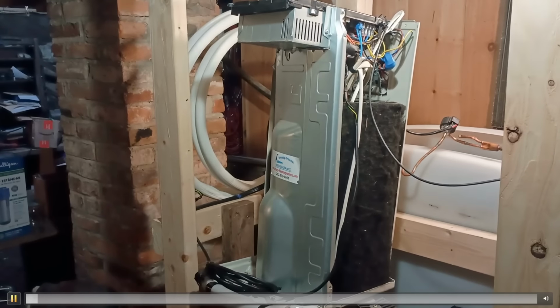The other problem with the ground source heat pumps is that they do not come in sizes that would really fit my house. I really only need something in the 18 to 24,000 BTU per hour range, and the smallest systems they make are on the order of at least 3 ton. So not a real good fit. So how did I size the system?